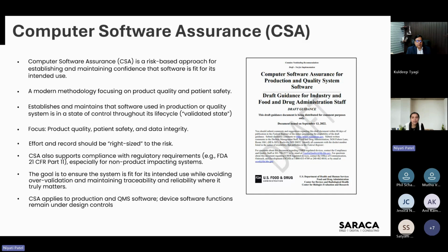And it really expects, FDA expects through this process to document your critical thinking. So you have to ask yourself why you tested what you did. This type of clarity will reduce wasted efforts and repeated testing or repeatability that you typically see with validations, and it'll make your audits easier. And evidence is really curated. You're building your rationale and documenting it. So definitely, when you go through audits and inspections, it'll make your process and your evidence easy to present to the auditors.